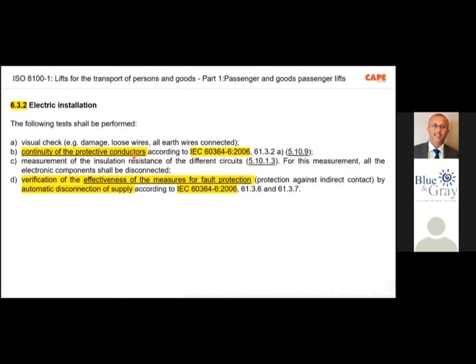Now let me go to the standard ISO 8100, which is the lift standard, passenger lift, clause 6.3.2. This clause talks about verification of electrical installation. The first one is, as usual, a visual check. The second one is continuity of protective conductors according to IEC 60364 part 6. As I told you, for all the basic things, 60364 part 6 is the base standard for any kind of verification in a low voltage installation. Now what you should do is check continuity of protective conductors.